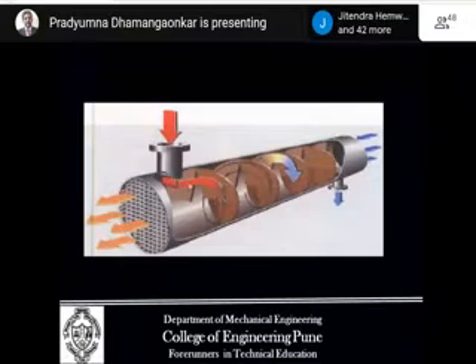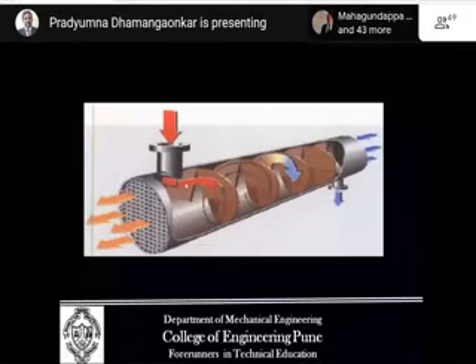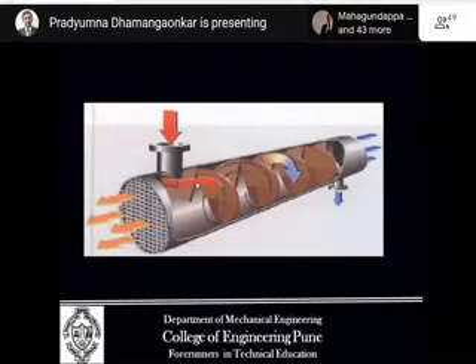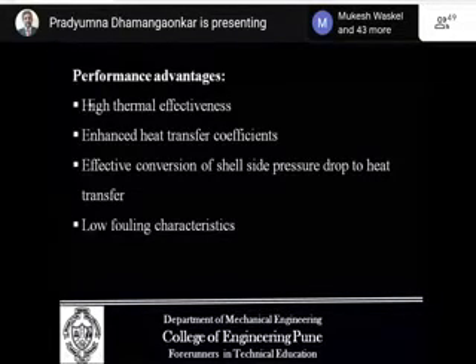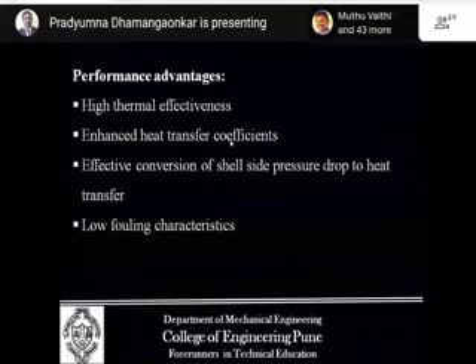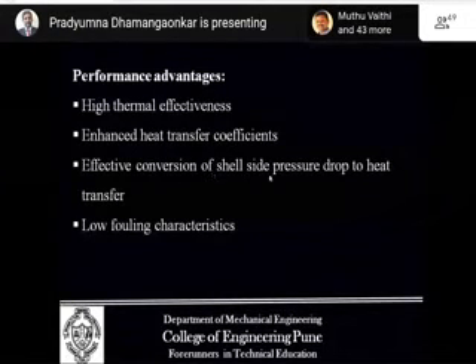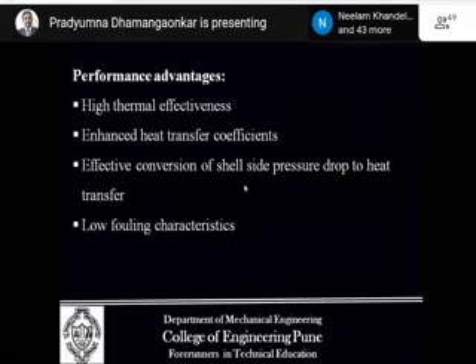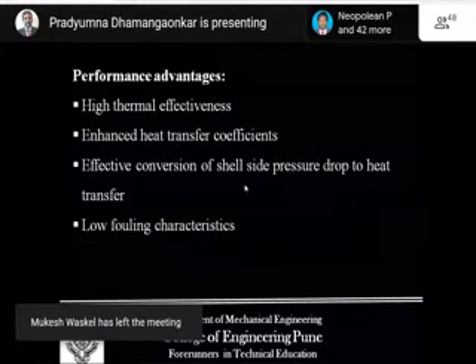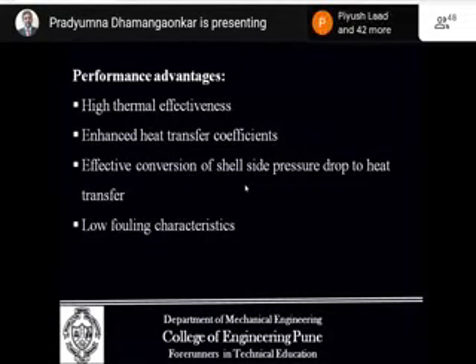Now there is a question: which angle will offer a higher heat transfer rate, or which angle will offer a higher heat transfer coefficient? The analysis is also done. The advantage is that higher thermal effectiveness is obtained, with an enhanced heat transfer coefficient and effective conversion of shell side pressure drop to heat transfer, because as there is no flow restriction, the fluid passage is very smooth. So there is less pressure drop, and this less pressure drop can be converted into a higher heat transfer rate.